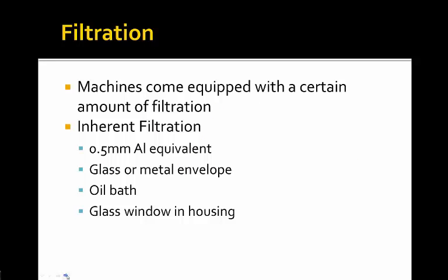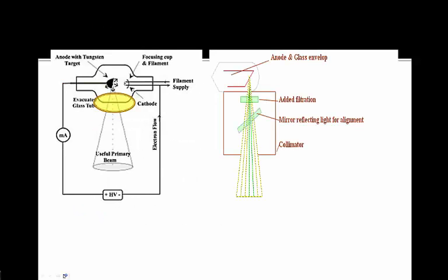Now we're going to cover filtration. Machines come equipped with a specific amount of filtration called inherent filtration. On our x-ray tubes it is 0.5 millimeter aluminum equivalent. It is also contained in a glass or metal envelope, sits in an oil bath, and has a glass window in the housing. The filtration is added right after the x-ray is produced at the anode — the x-ray beam passes through the added filtration and then comes down through the collimator to our patient.